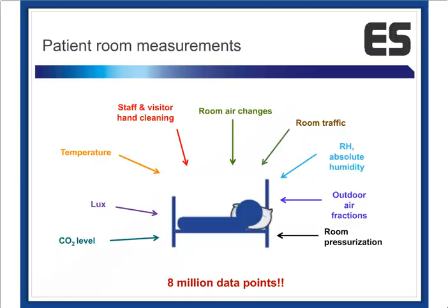What we found was this: the indoor variable that was most statistically significantly related to new patient infections was indoor relative humidity—not absolute humidity, but relative humidity. On the x-axis, starting in winter, going through summer, and back to the next winter, the red columns are the number of healthcare-associated infections during those months, and the blue line is the average relative humidity of all 10 rooms. They were all very closely related.